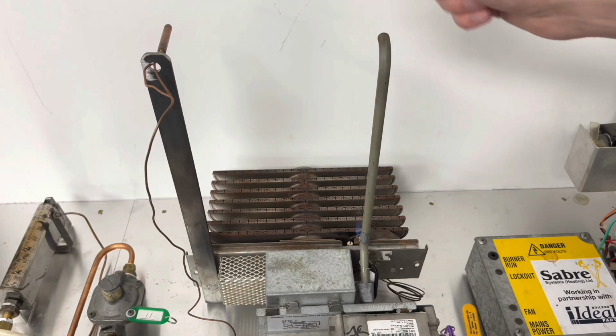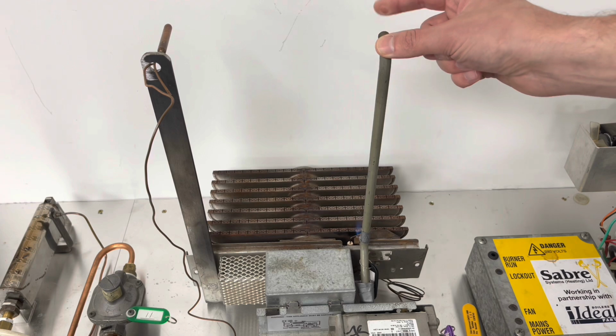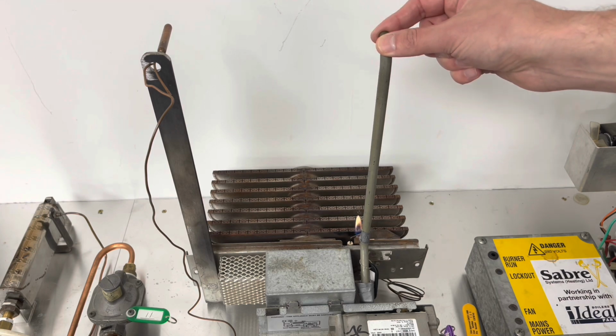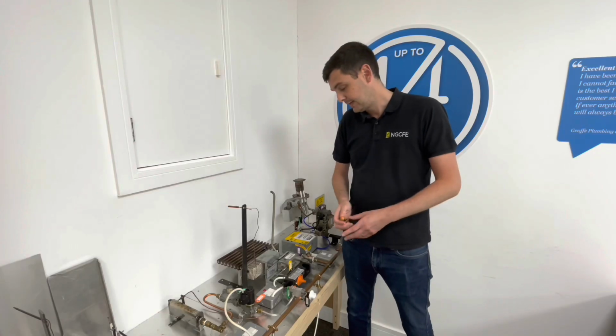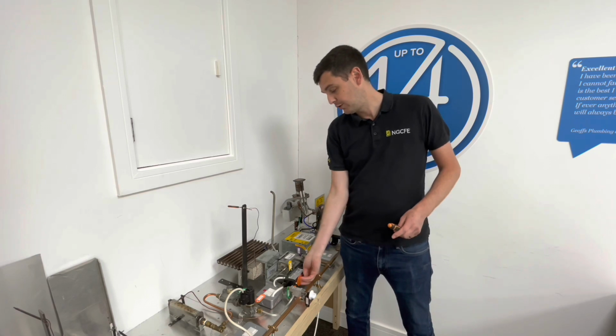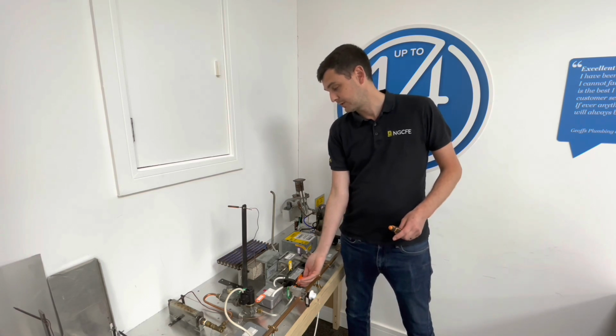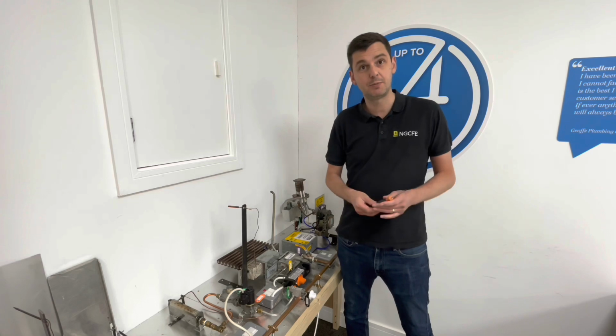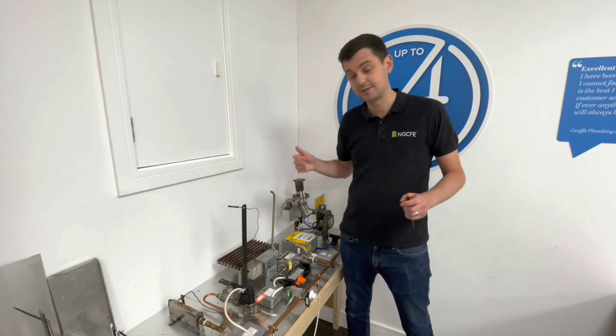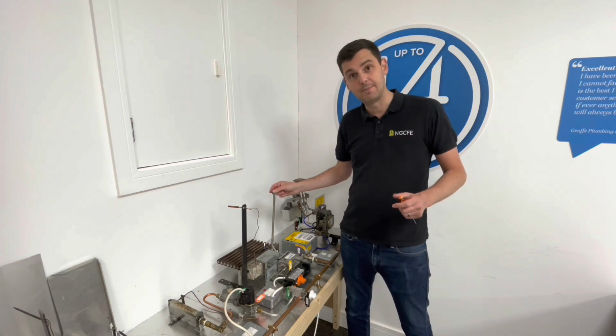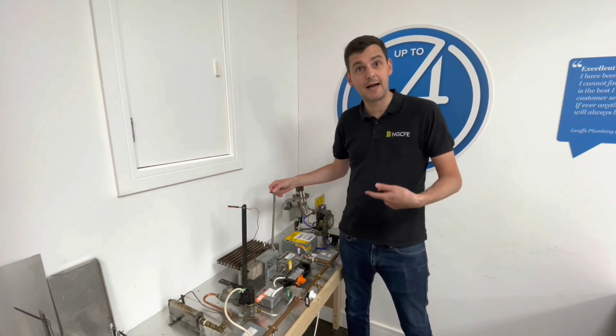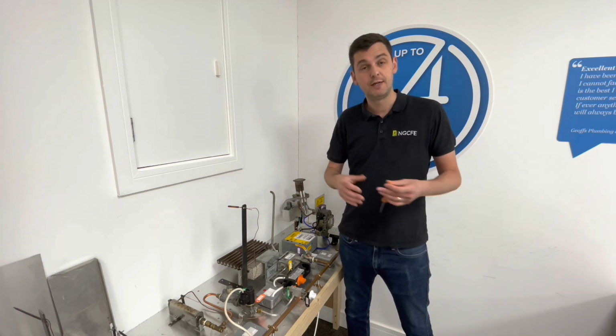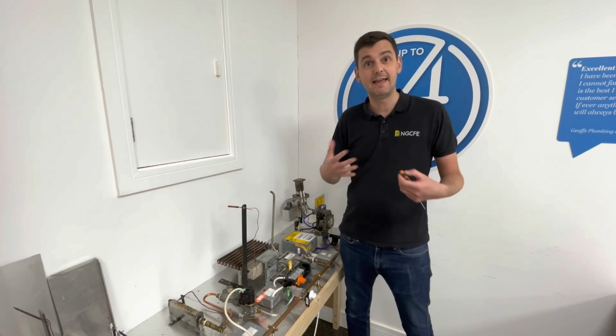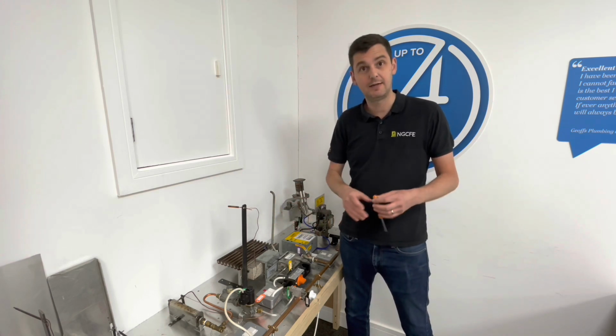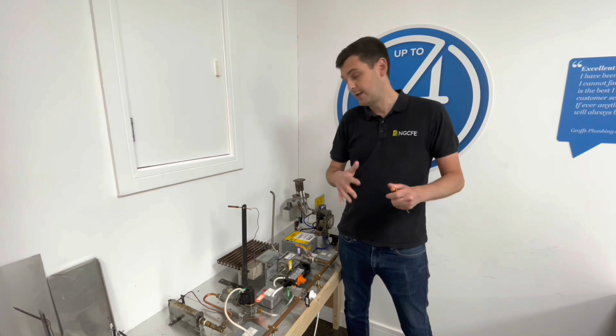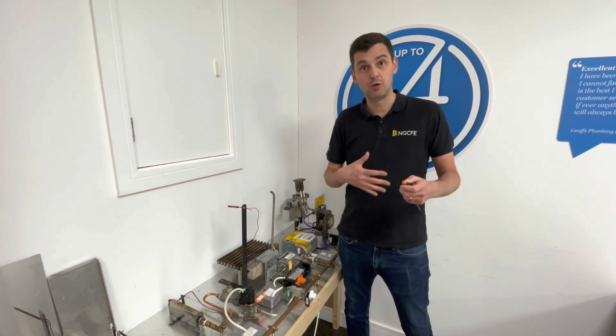It would make the pilot light go vitiated, and then the thermocouple will cool down. And that's what it's meant to do. So if you were servicing this appliance and you were testing the oxygen depletion sensor, you would put your finger over that and you would expect the pilot light to go yellow and orange. So you're taking its air for combustion away from the pilot light. When you do that, it should go yellow. That's what you want it to do.